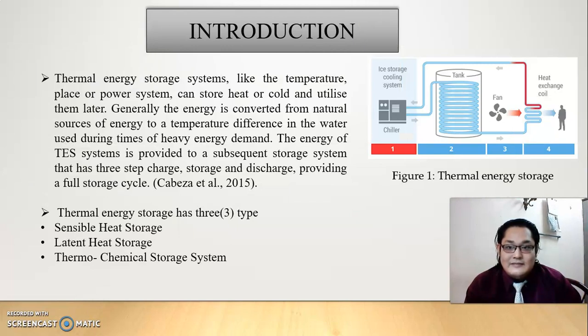Introduction. A thermal energy storage system is like a temperature or power system that can store heat or cool and utilize them later. Generally, the energy is converted from a natural source of energy to a temperature difference in the water, used during times of heavy energy demand, which is our office hours, 8 a.m. until 5 p.m. The energy of the TES system is provided to a subsequent storage system that has 3 steps, which are charge, storage, and discharge, providing a full storage cycle.